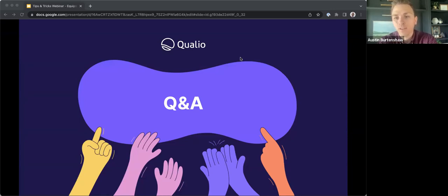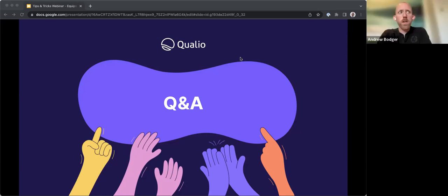Thanks for that question. A question from Kelly. Can you attach or upload to an asset to record calibration certificates, IQ, OQ, PQ, protocol reports, user manual, etc.? Yeah, so I think you can upload these documents in a few different places. I think the one that I first recommended would be in the equipment file. So you'd have your document there, and we had an attachment section at the end in our example.